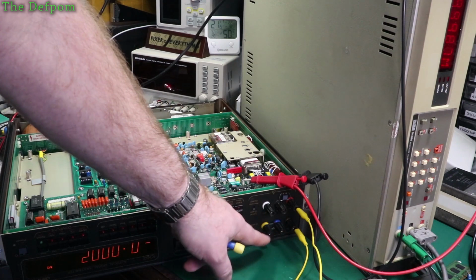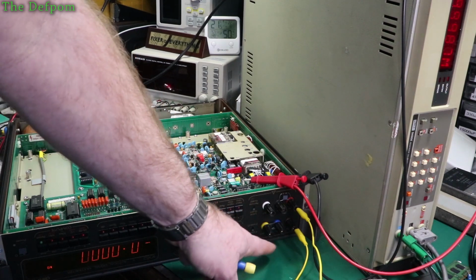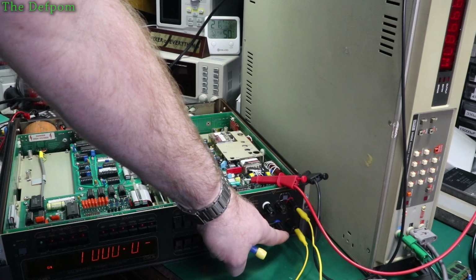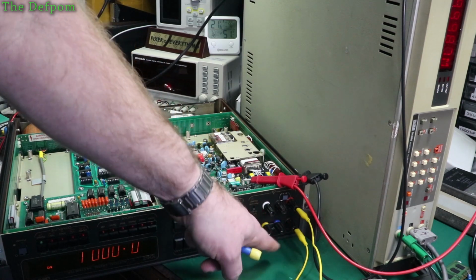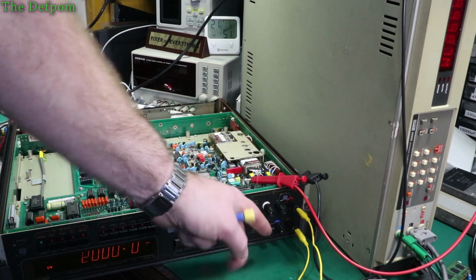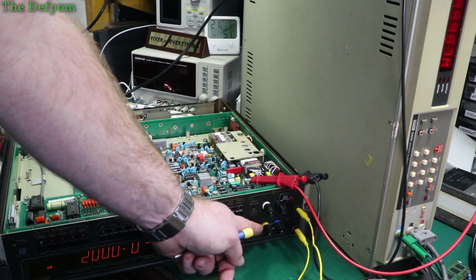I've got one of those metal bars between the ohms guard and the I negative. And you have to link these 2 terminals together. But because they're not standard spacing, you can't just use one of these little metal links. You have to use a jumper, which is a bit of a pain. Wish they were standard spacing apart. It'd be a bit easier.